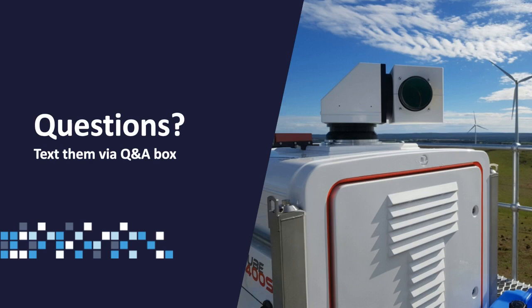So if you imagine that you have a turbine and a met mast, you will probably restrain the sector for, I don't know, plus minus 30 degrees with the alignment of the turbine and the met mast. That could be a potential setup, but it would be this narrow sector. While if you have a Nacelle lidar, you are always pointing towards the wind, so you can have a way wider sector, having more points, being then faster to have a power curve. That's the idea.